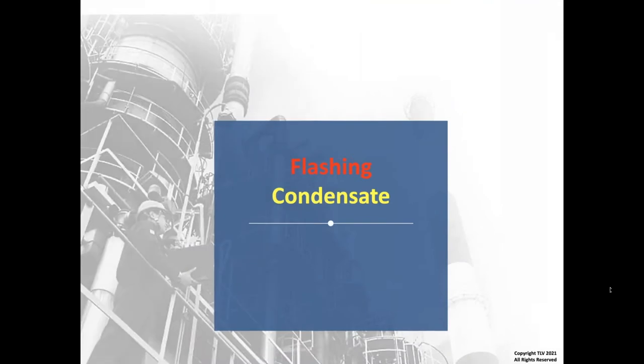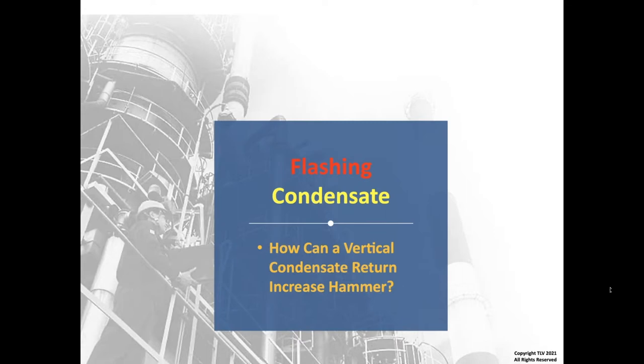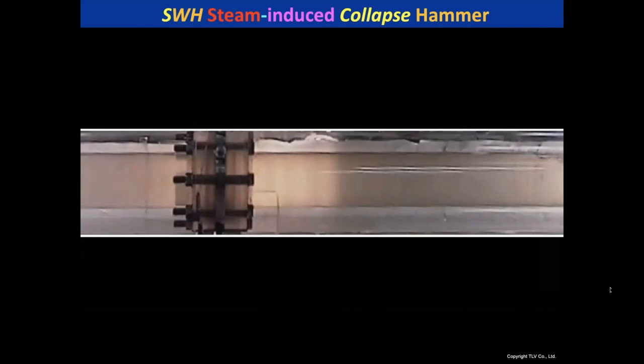The next concept I want to discuss is flashing condensate and how it creates hammer with a vertical return. From the first presentation, we had acrylic piping in the R&D lab at around 7 or 8 psi — watch how quickly the pockets dissipate in the horizontal line. Whenever you go from high pressure out of a steam trap to low pressure, you get flash steam. Watch how quickly that can dissipate.